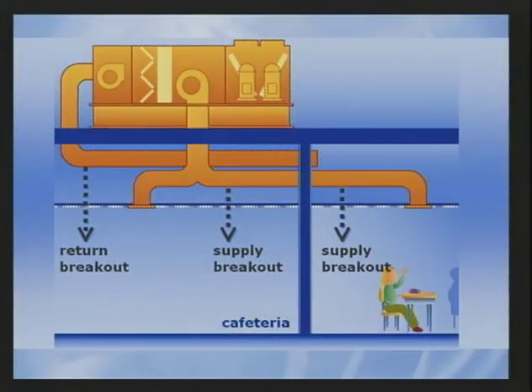duct breakout sound. The duct breakout path accounts for sound that resonates through the duct wall. This sound path is possible in any section of ductwork, but it is of greatest concern on large aspect ratio rectangular ducts near the sound source. Think of the large flat surface of these ducts as the diaphragm of a speaker and the sound pressure inside the duct as the driver. This arrangement is very effective at radiating sound. As a result, it's important to avoid routing main supply or return ducts over sound-sensitive areas.